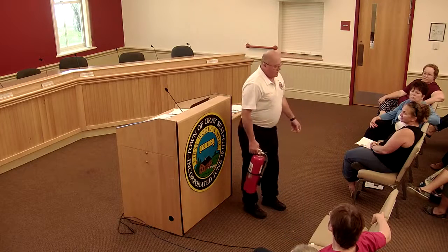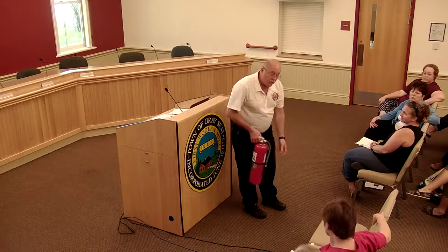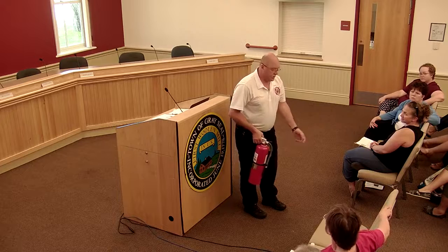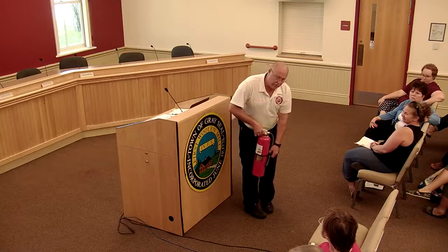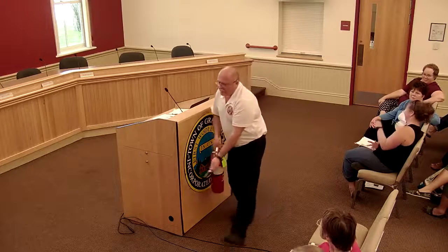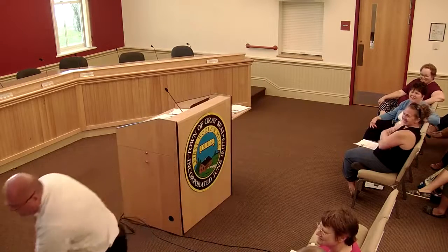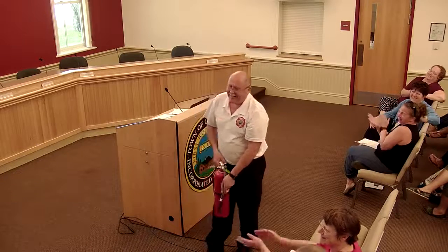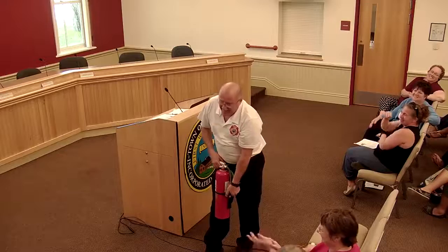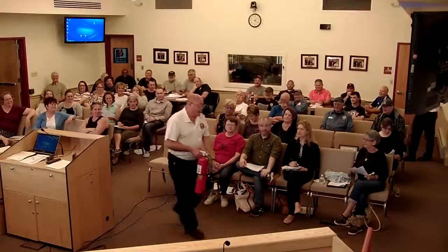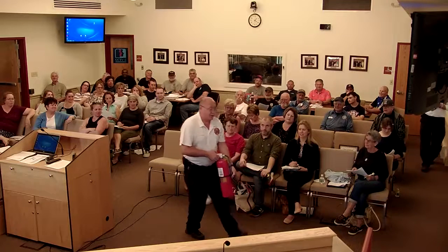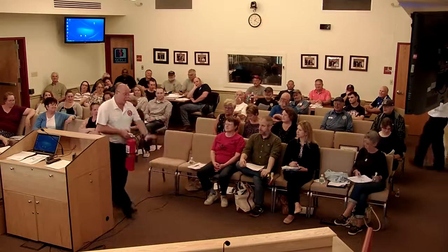We also teach to make sure your extinguisher works before you walk it up to the fire. We're going to start from here, with the extinguisher, and then walk up to it. The other thing we teach is that we never turn our back on the fire. So once the extinguisher's empty, walk backwards, so you know what's going on.